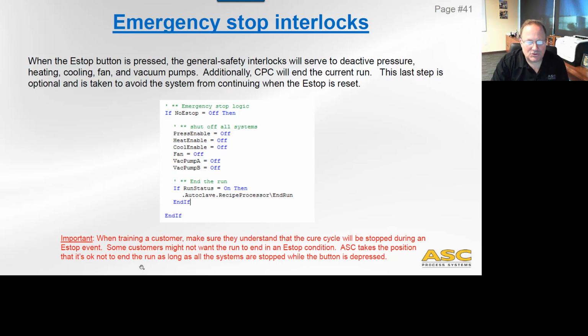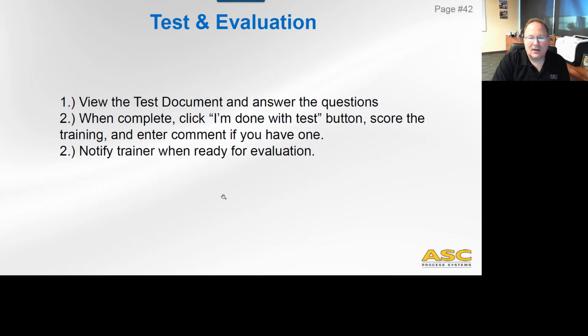Now, when training a customer, make sure they understand that the cure cycle will be stopped during an e-stop event. Some customers might not want that to happen, and they might ask you not to put that in there. And ASC takes the position that it's okay not to end the run as long as all those other systems are stopped while the button is actually pushed in. So this should be our standard. But again, talk to the customer about it. And most of them are going to want the run to end if someone e-stops it.